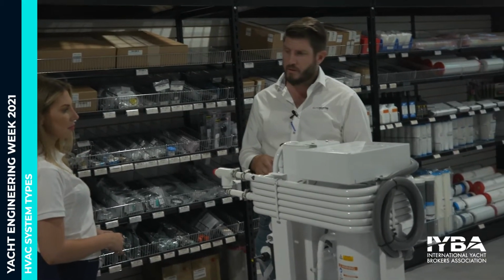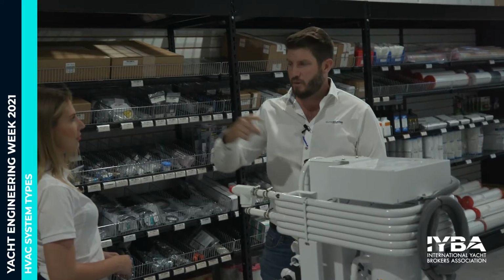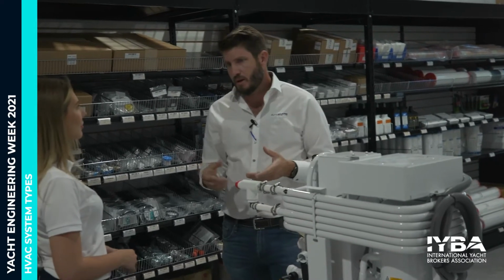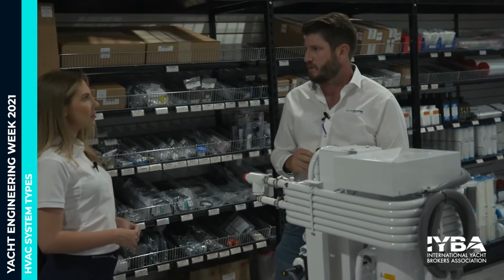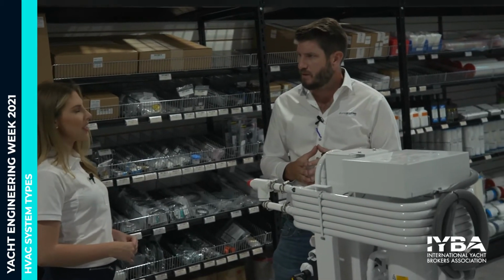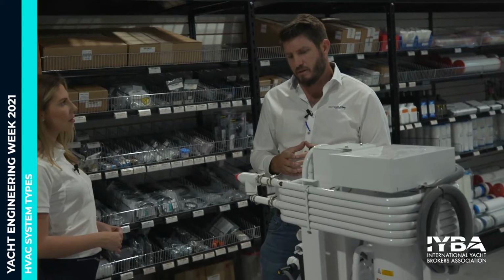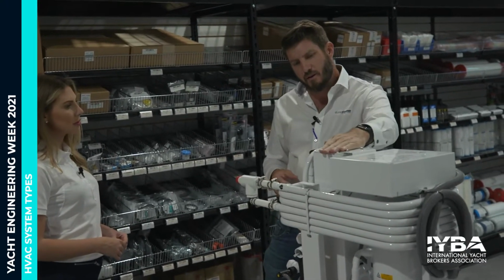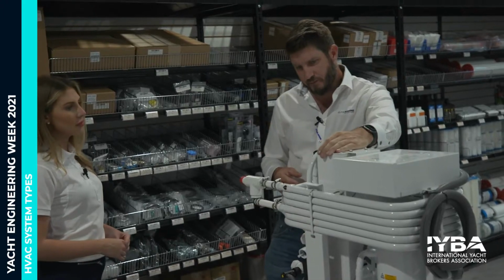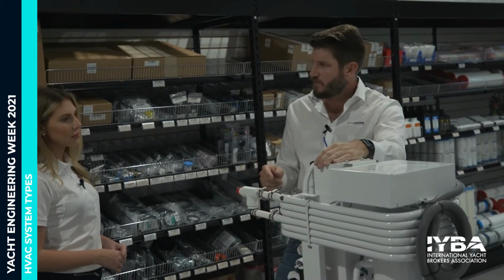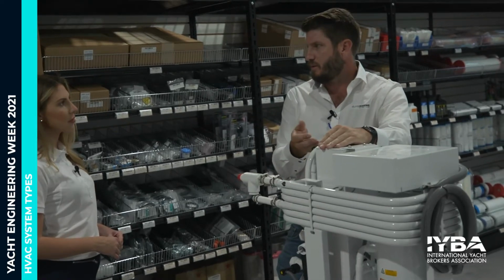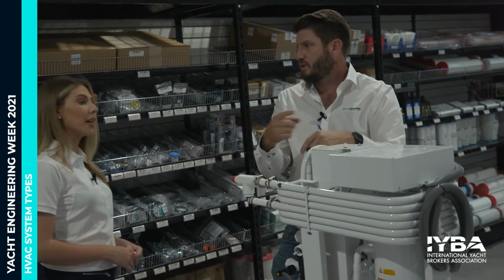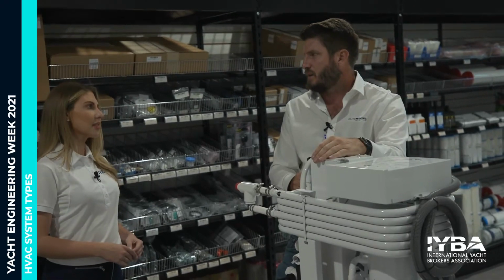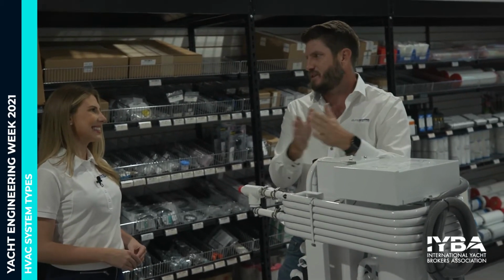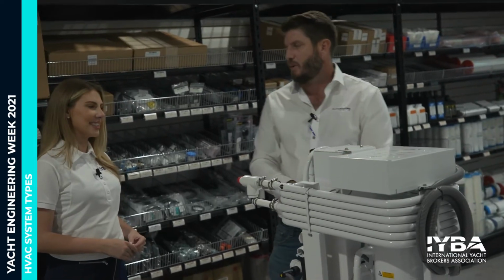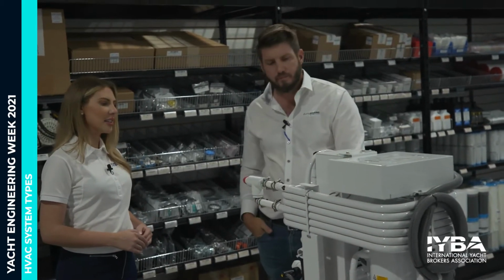In the chilled water loop, remember there's a second loop of water going through the boat. It's a freshwater loop. We just want to make sure there's a glycol mixture in that loop to protect the chiller. What does that do? The glycol prevents spot freezing, because remember our evaporators here, we've got very cold refrigerant, and then we've got water flowing past it. If the water flow is obstructed, it could slow down and you could get spot freezing of the water, which could escalate to a domino effect. We don't want to see that, because then the water freezes, it expands, and then this cracks. That's why we like to see glycol in the chilled water loop.